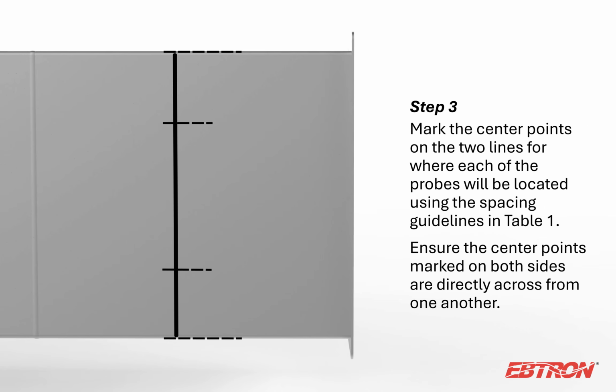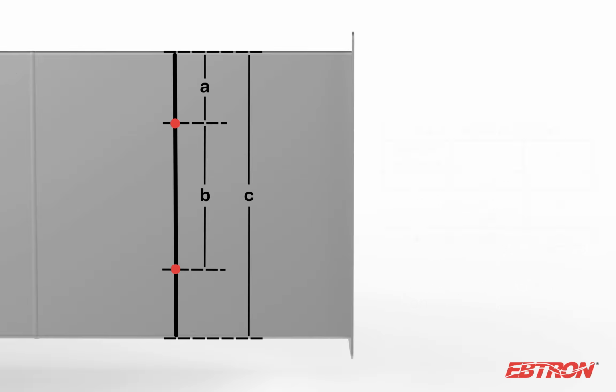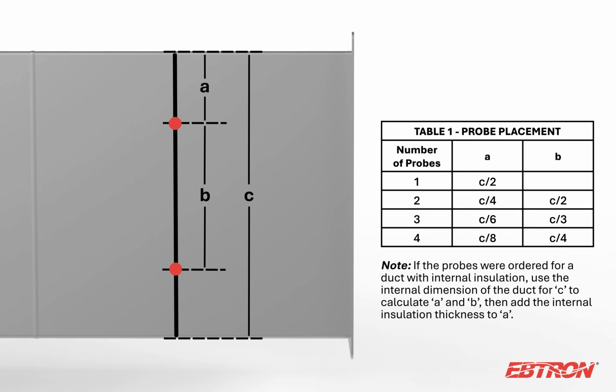We will then mark a center point on the two lines where each probe will be located using the spacing guidelines indicated in Table 1. In this example, we will be installing 2 probes. If more than 2 probes are to be installed, continue spacing additional center point marks at the B interval from the previous center point. Ensure that the center points marked on both sides of the duct or opening are directly across from one another.